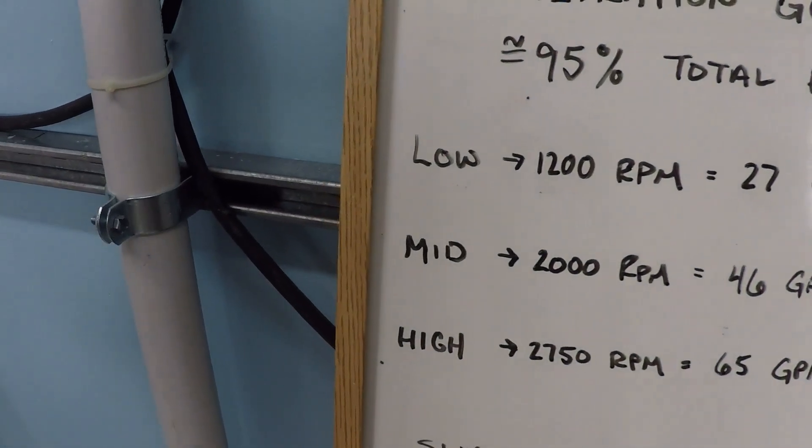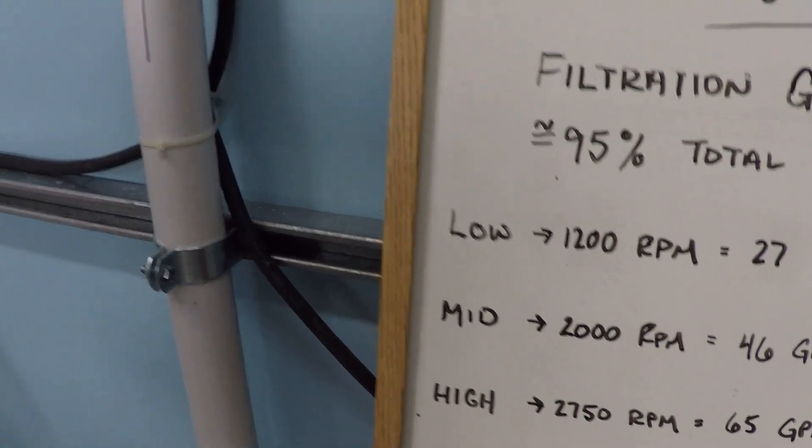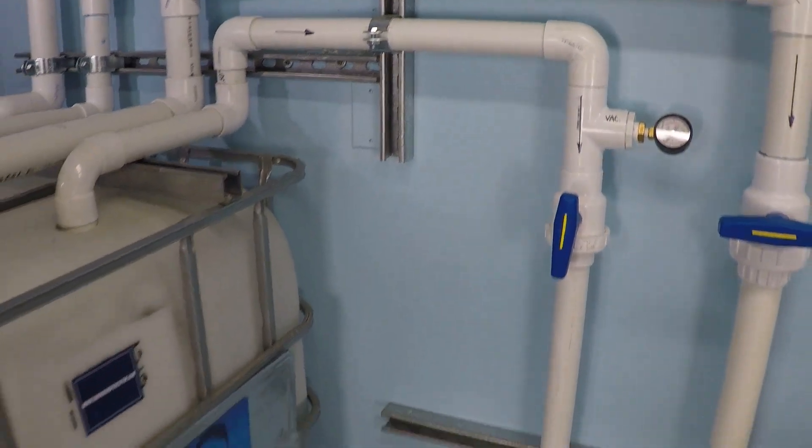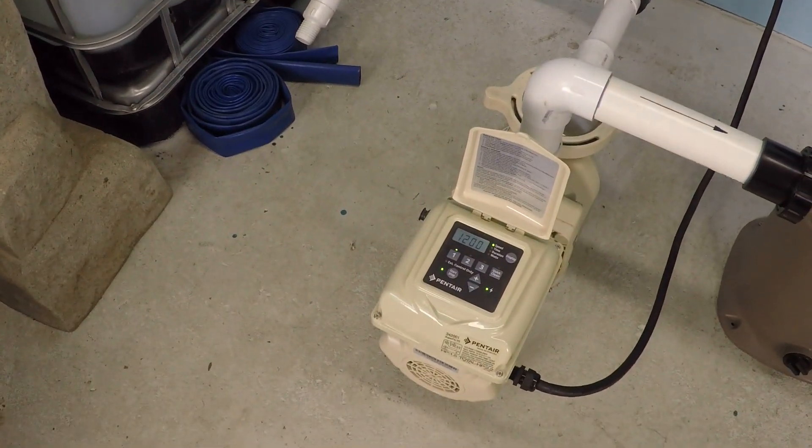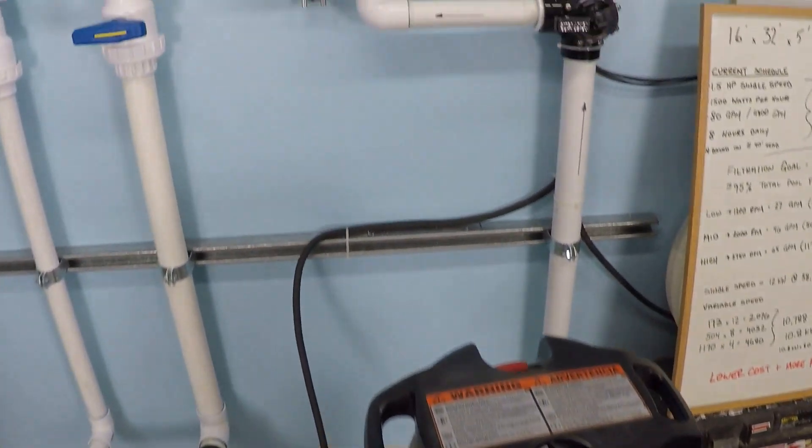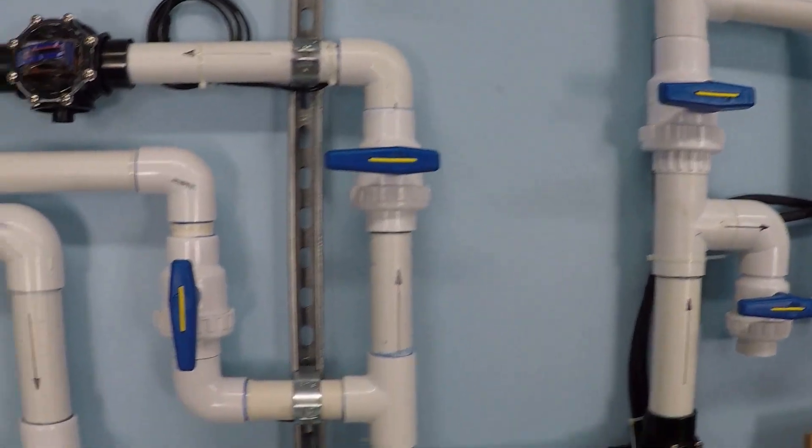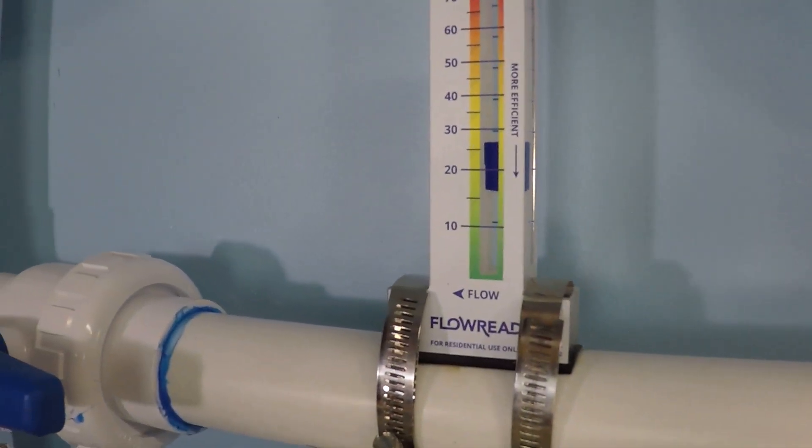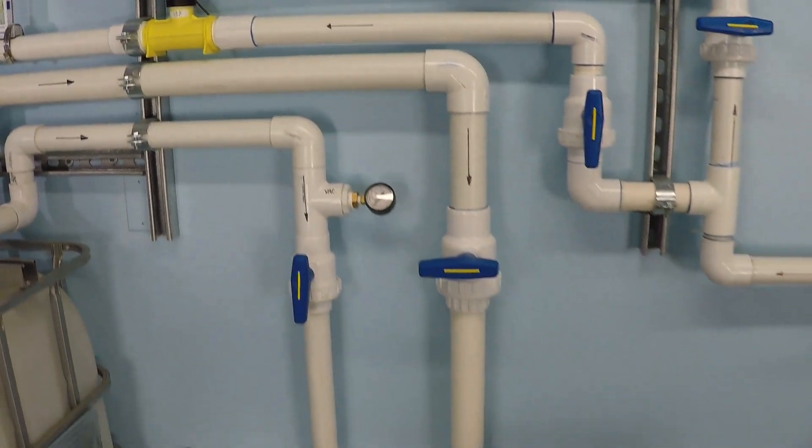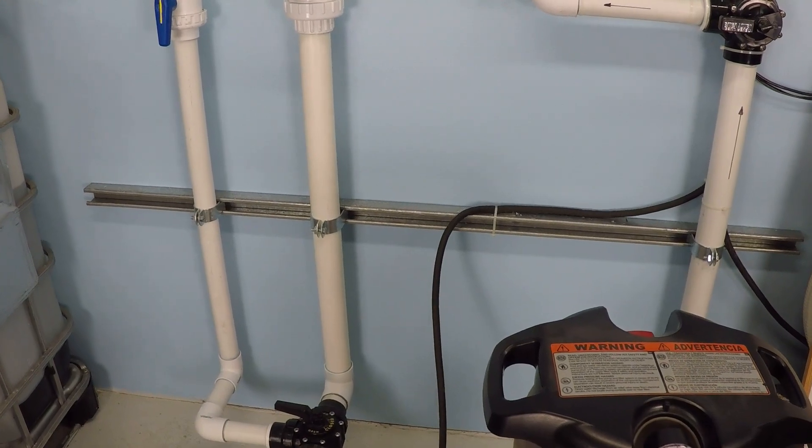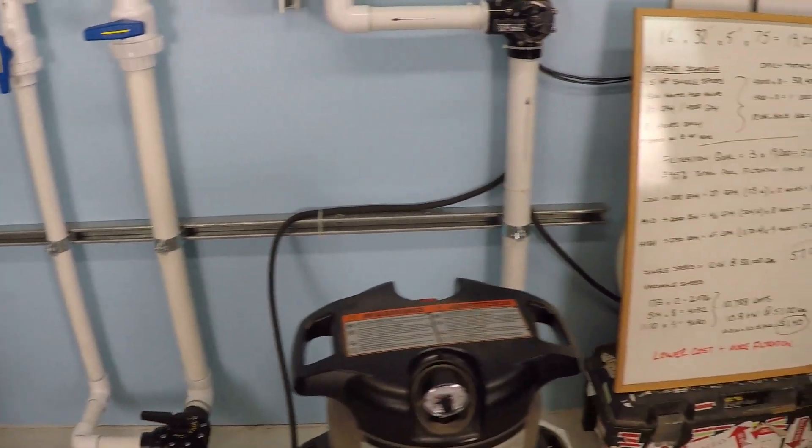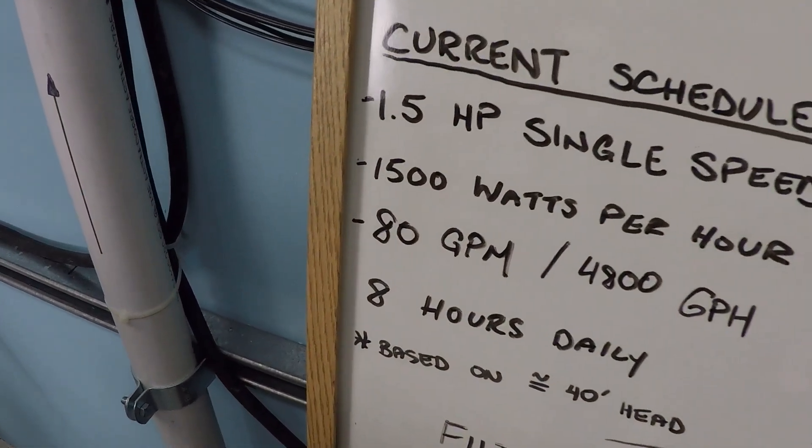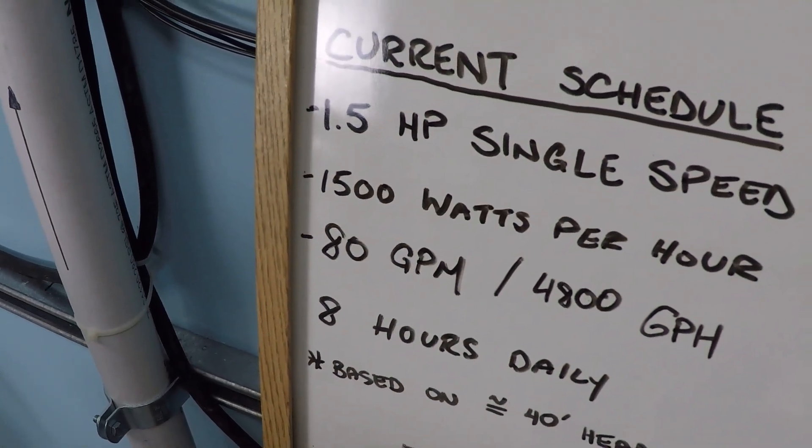Let's take a look at the pump setup. The pump is set up for 1.5 inch plumbing, a single section line, 1.5 horsepower pump, 150 square foot cartridge filter. That line is isolated, we're only going through this inch and a half line through this digital flow meter and analog flow meter. Under maximum flow, we see that this system is approximately 40 feet of head resistance. That allows us to make some calculations. You can use a flow curve to determine what an average pump might get in terms of flow rate.